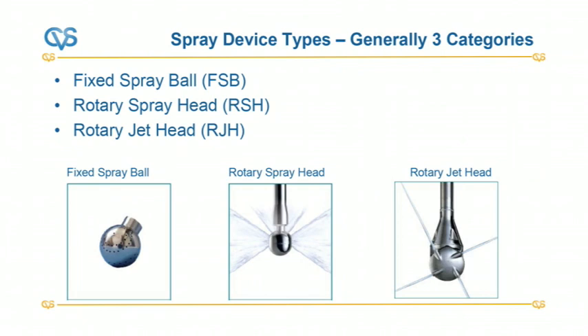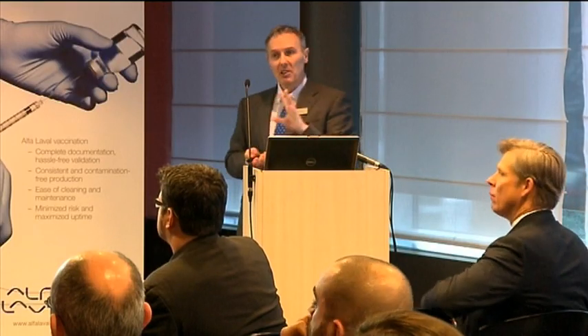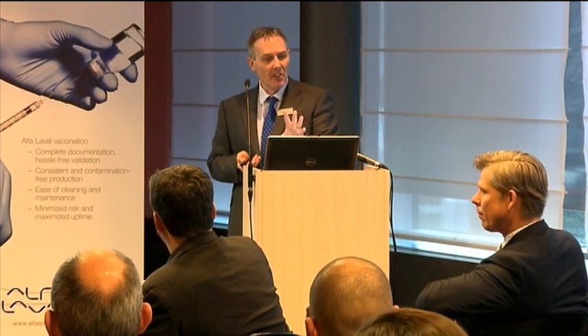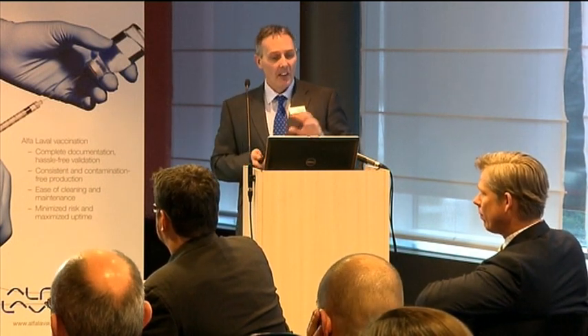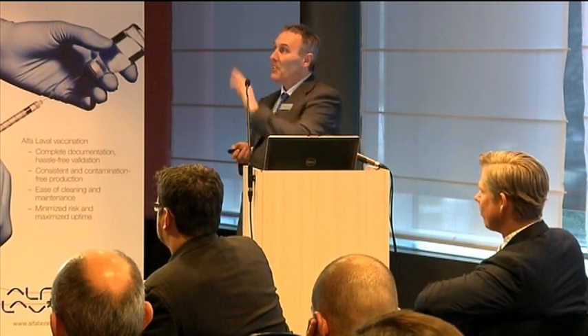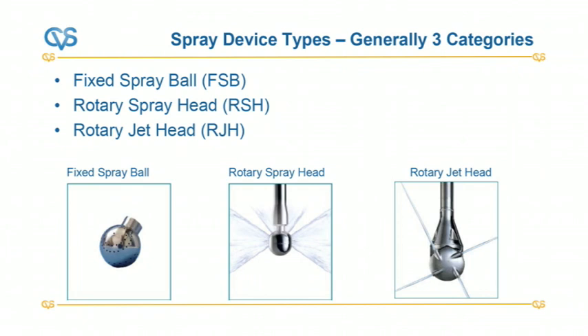So, spray devices. There are lots and lots of manufacturers and lots of different types, but on the theme, there are generally three categories. Thanks to Alfa Laval for these photographs. There's a fixed spray ball, which is basically custom drilled, like this one here, so it's locked in position and these holes are drilled such that they spray in various locations. There's a rotary spray head, which can spray a fan of water around the vessel. So rather than having water running down the sides, we're actually having water hitting the sides of the vessel as well as the lid, so we're increasing the impact in that case.